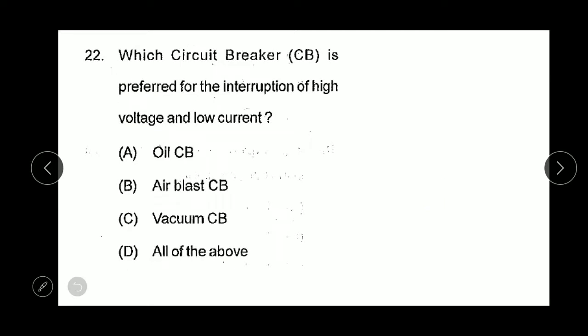Next question 22: which circuit breaker is preferred for the interruption of high voltage and low current? This is air blast circuit breaker, but currently air blast circuit breakers are not used, only somewhere in old grids. Now these are replaced by SF6 circuit breakers.